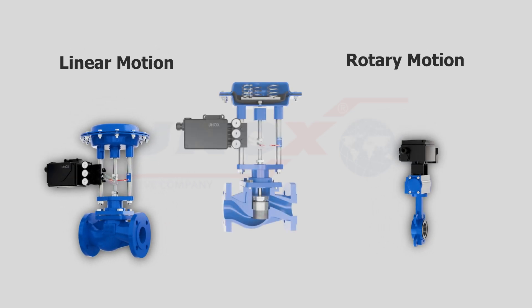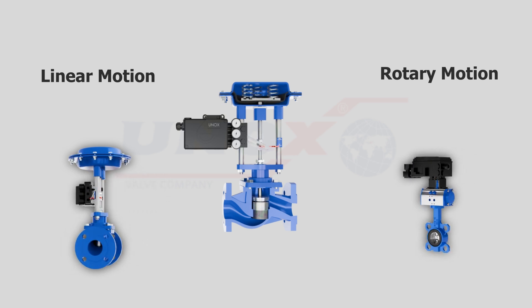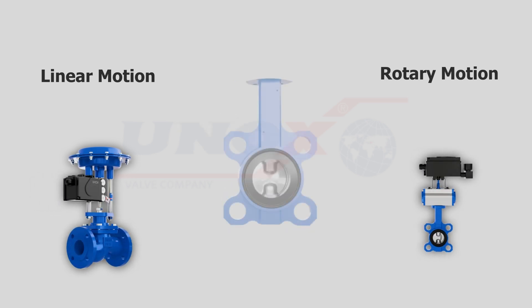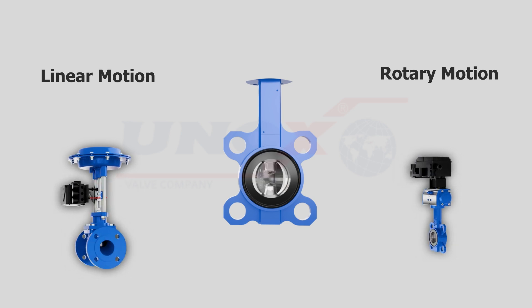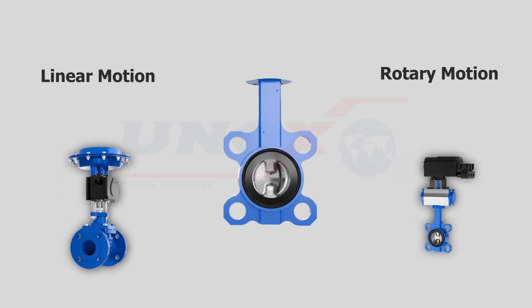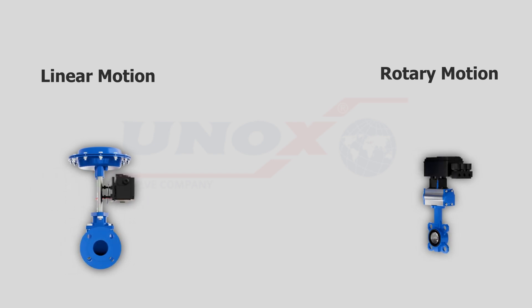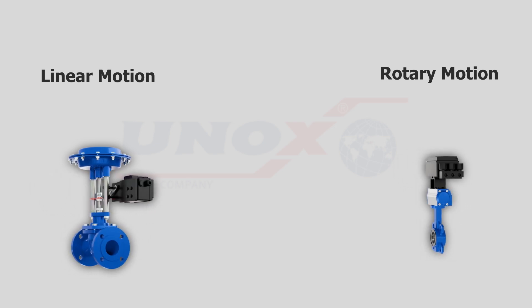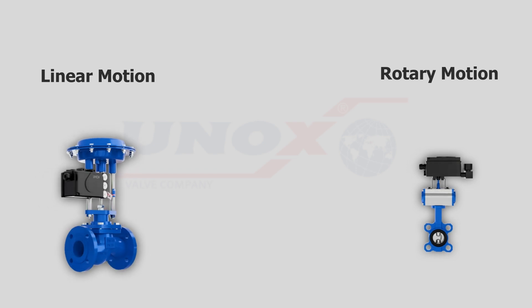In a linear motion valve, the stem and plug move up and down. The most commonly used type of linear motion control valve is the globe valve. A rotary motion valve generally turns 90 degrees to move from the open position to the closed position in most cases. A commonly used type of rotary motion valve is the butterfly or ball valve. An actuator is a power unit connected to the valve that provides the necessary force to open and close it. An actuator can be controlled electrically or pneumatically, and the most common and most reliable type is the pneumatic actuator.